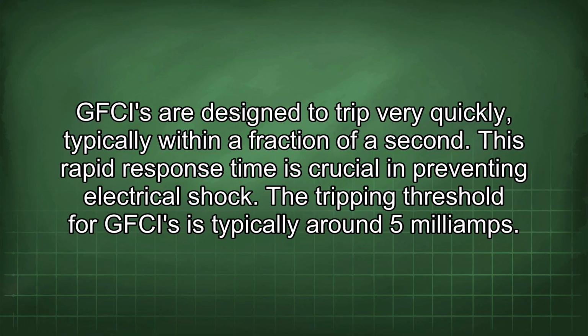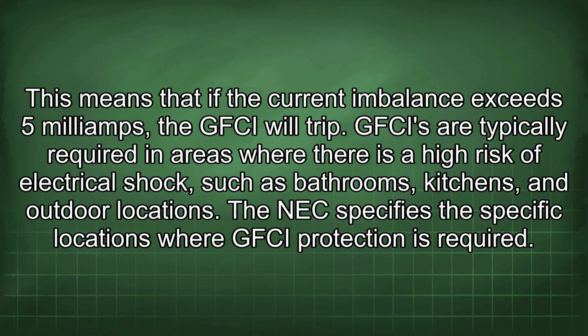GFCIs are designed to trip very quickly, typically within a fraction of a second. This rapid response time is crucial in preventing electrical shock. The tripping threshold for GFCIs is typically around 5 milliamps. This means that if the current imbalance exceeds 5 milliamps, the GFCI will trip.